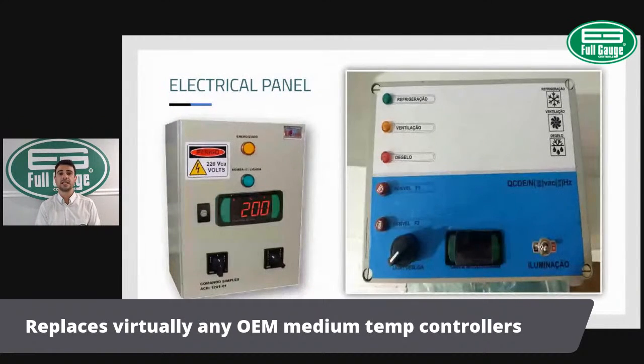So they can actually add a contactor when they have loads higher than 2 horsepower, because the 512, the MT512 provides you 2 horsepower relay output. That means you can hook up your compressors up to 2 horsepower direct into the controller terminal. There is no need for external relays or contactors.